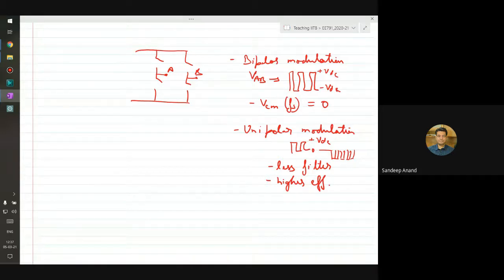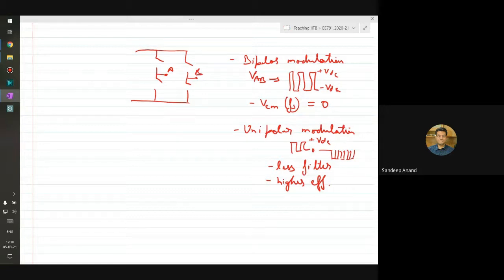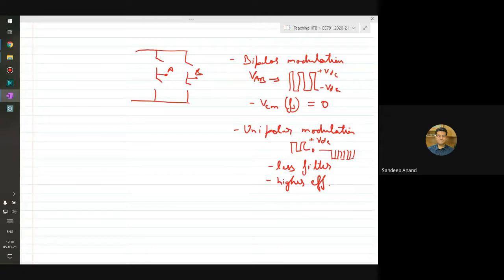But the catch is, as we discussed, that in unipolar modulation there is a common mode high frequency voltage which forces common mode leakage current. So if you see somewhere between 2000 to 2010, when solar was becoming more and more popular, people could figure out that this is the problem. You can make a bipolar based inverter but the leakage current won't be there - however it will probably not be as efficient. But if you go for unipolar, you can improve efficiency, but then there's a leakage current problem.